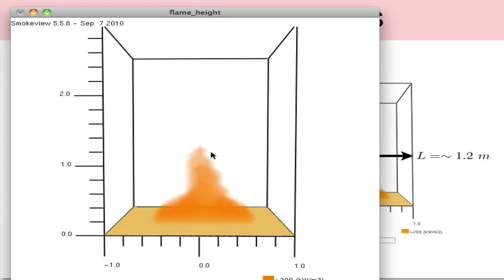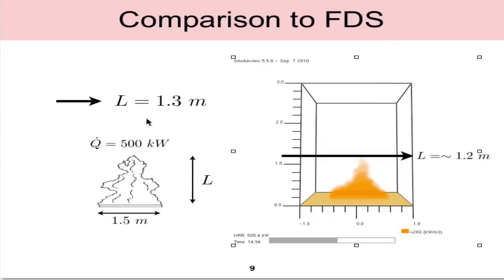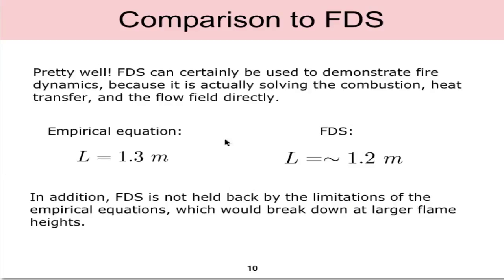From the simulation we can see that the flame height predicted is about 1 to 1.2 meters and how well does that compare to our empirical answer of 1.3 meters? It turns out that it's pretty good, it's pretty close. 1.3 meters, 1.2 meters. In this case FDS can certainly be used to demonstrate fire dynamics because it's actually solving the combustion, heat transfer, and the flow field directly.